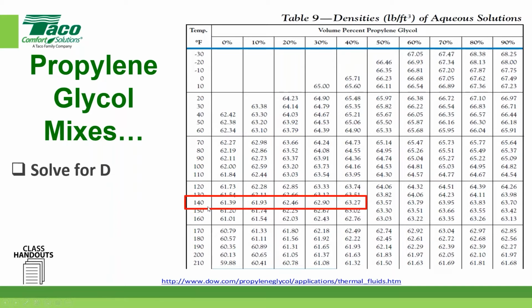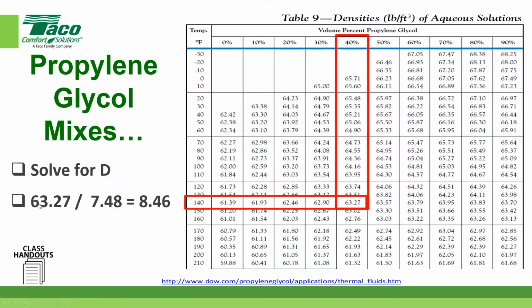So we just put the temperatures in there. We put the mixtures in there. I'm using 40% for now. And I see that a cubic foot of that product at that temperature weighs 63.27 pounds. Now, here's a longhand version. I take that 63.27 divided by 7.48 because that's how many US gallons are in that cubic foot. And it tells me that 1 US gallon of that product now weighs 8.46. Okay. It's a longhand version of doing it. And then we take that result here and we times it by the specific heat, which will be another lookup table we're going to go to next.